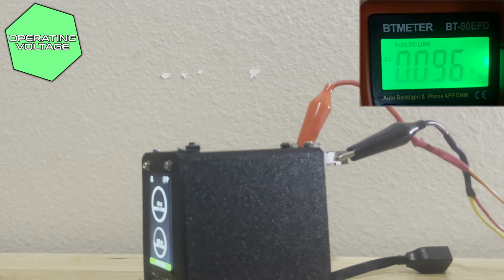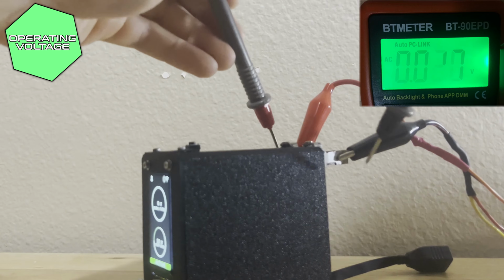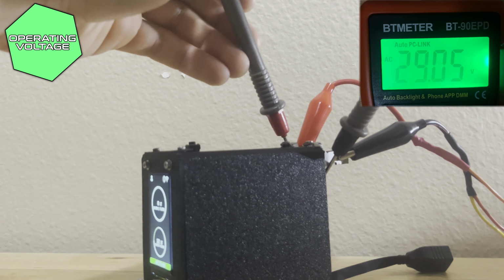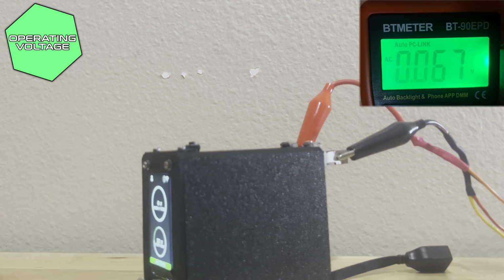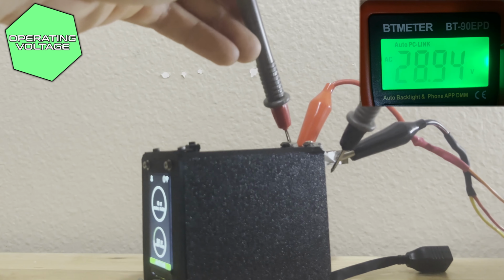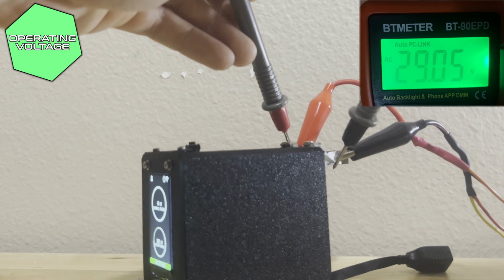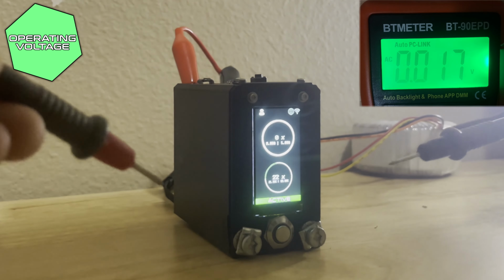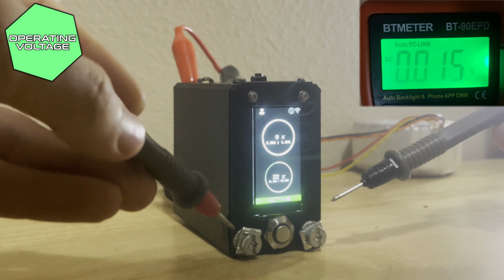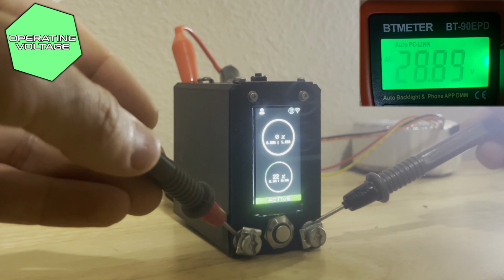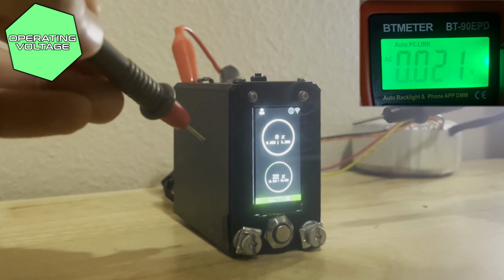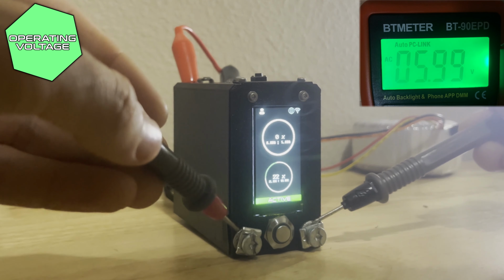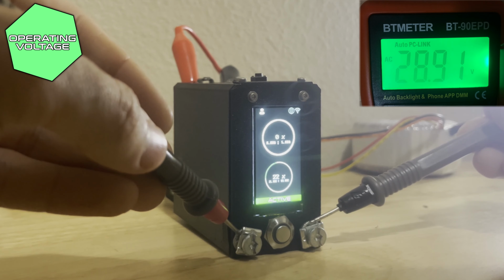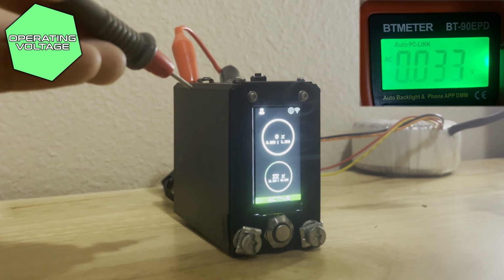Alright, so we're just going to showcase the voltage at the terminals. So at the back terminals where the simulation grid directly connects to it, as you can see, about 30 volts AC. We'll go again and measure it. As you can see, it's still about 30 volts AC, a little under 29, 28 terminals. So now we'll move over to the front terminals, which actually connect to the load. And while it's active, as you can see, getting about 29 volts once again, AC. Take it off, do it one more time.